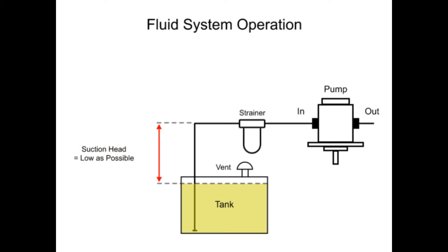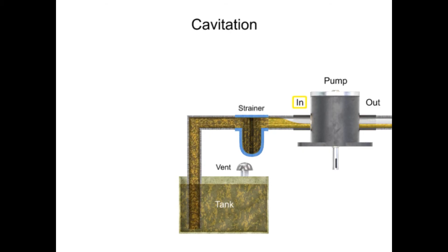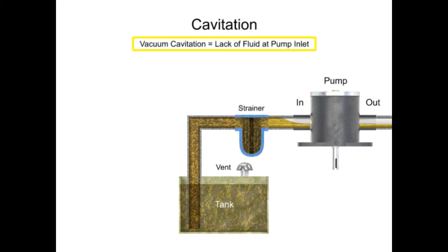Several issues may occur if enough fluid does not flow to the pump inlet. One such scenario is called cavitation. The most common form occurs when the inlet fluid is not entirely filling the cavities which open up for it on the pump inlet. This type is called vacuum cavitation, commonly known as starving the pump, because not enough fluid makes it to the inlet.